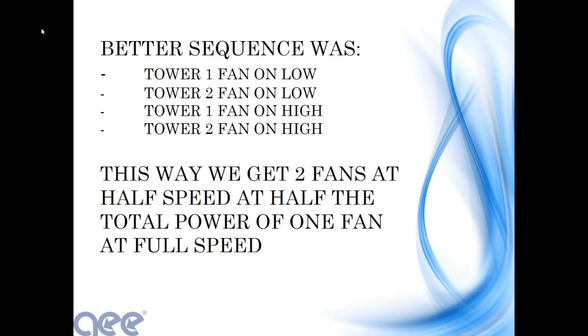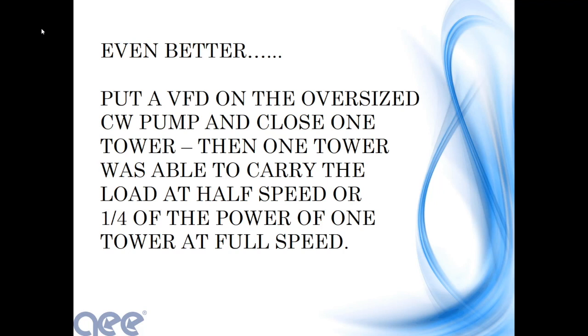So we went out, flipped a couple of valves at the head end of the building automation system, and ran half water flow through 2 towers, and they worked fine. The fill was completely wet. We didn't have any problems at all running the towers at half water flow. Even better than just changing the sequence was to put a VFD on the oversized condenser water pump and close off the other tower, only run 1 tower.